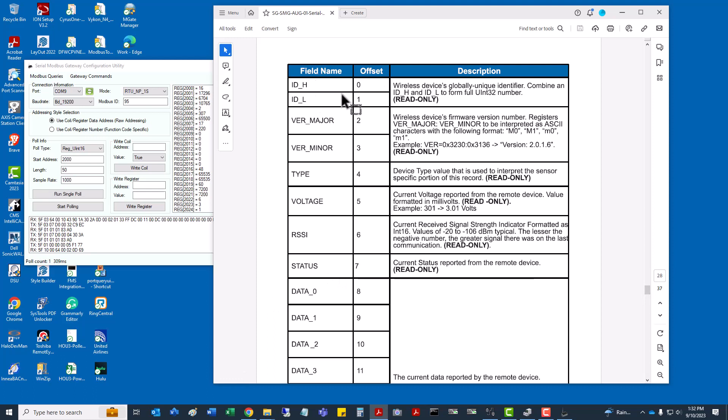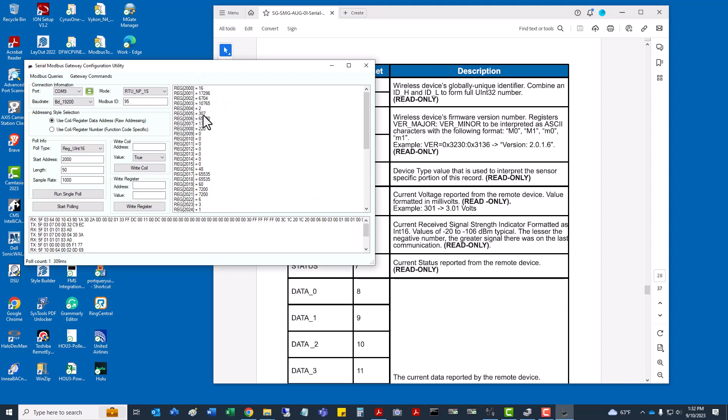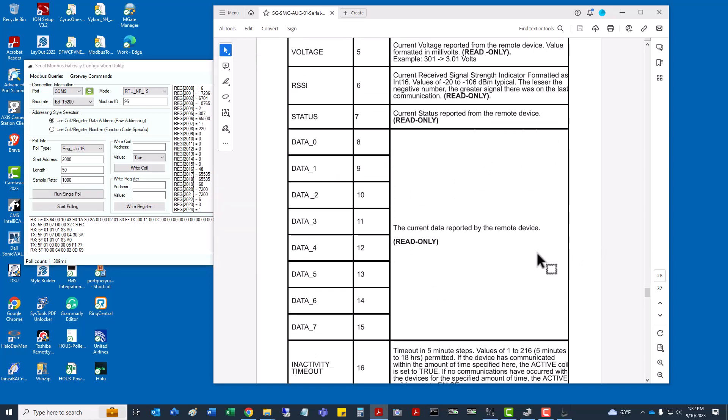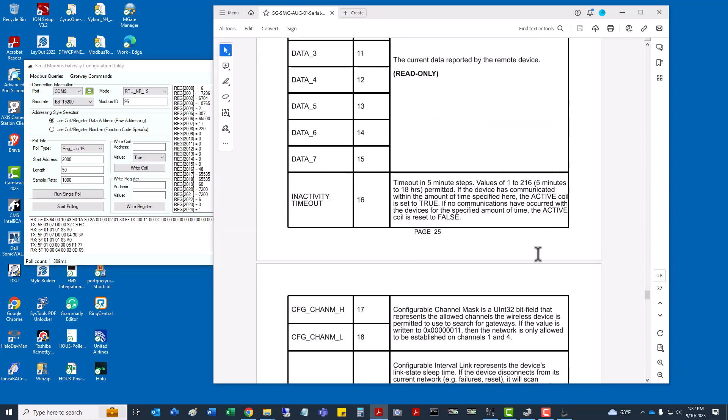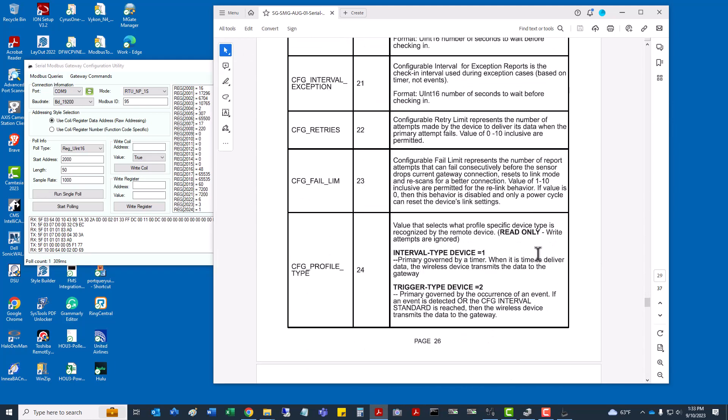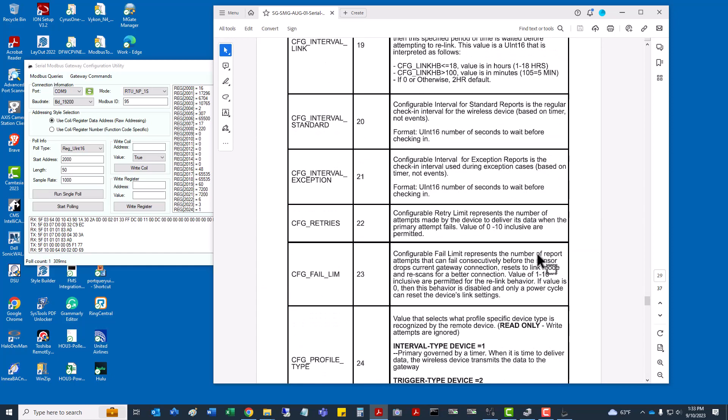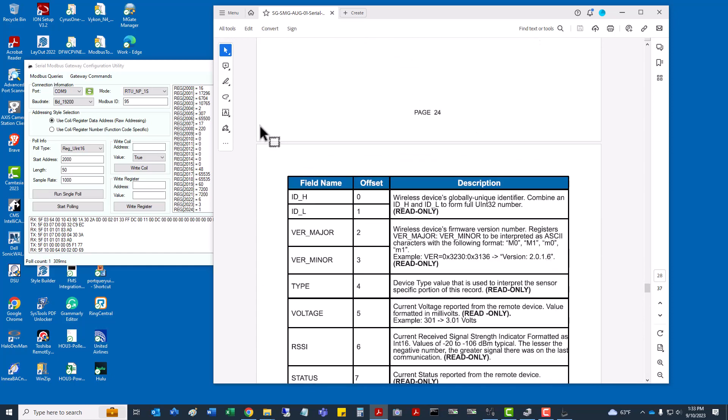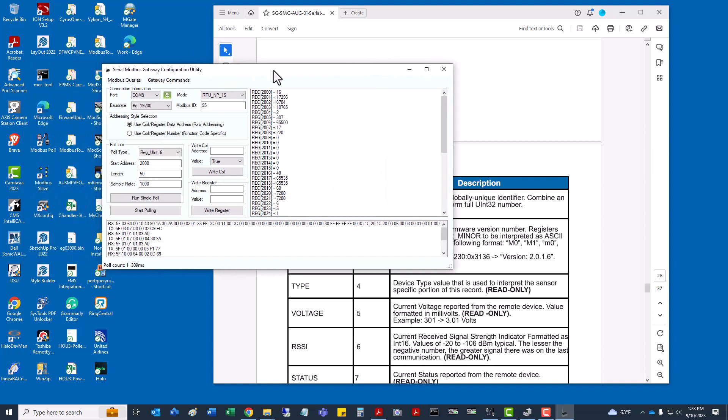Depending on your controller, you might have to increase the register by one all depending on what type of platform you're reading in on and what your options are. If you go back over to the PDF, there's a section Wireless Device Register List. This starts showing what everything represents. We have some floats, unique identifiers, firmware version, sensor type, voltage. So it's 40005 or 40006 depending on your platform. If you look at 5307, it's battery volts. This sensor uses two 1.5-volt double-A style batteries. Once we apply the scale, we're at 3.07 volts, so that's good.